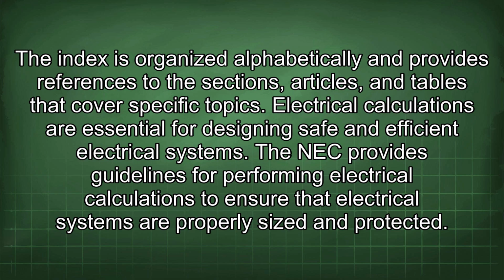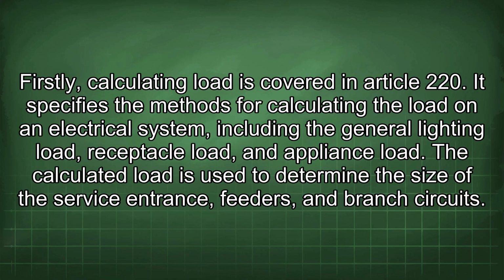Electrical calculations are essential for designing safe and efficient electrical systems. The NEC provides guidelines for performing electrical calculations to ensure that electrical systems are properly sized and protected. Firstly, calculating load is covered in Article 220. It specifies the methods for calculating the load on an electrical system, including the general lighting load, receptacle load, and appliance load. The calculated load is used to determine the size of the service entrance, feeders, and branch circuits.